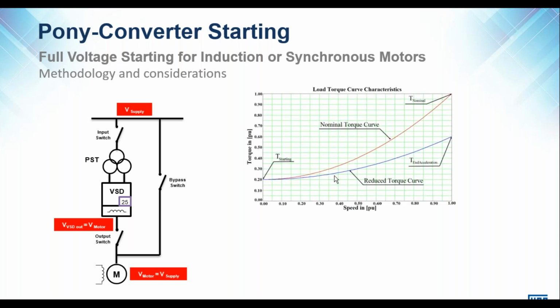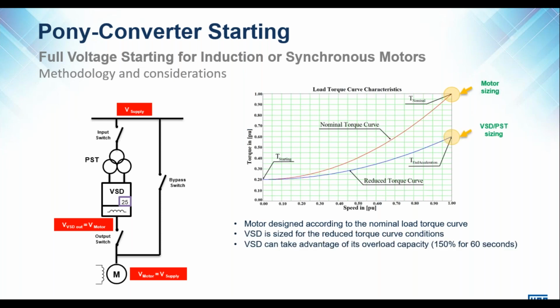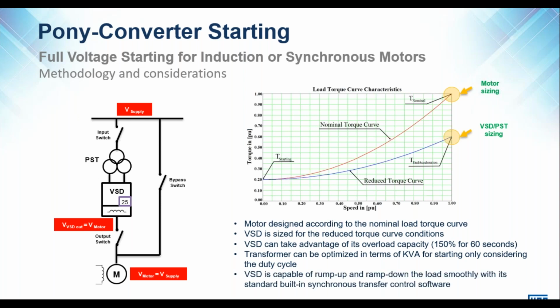This curve you recognize from earlier. We have the blue curve, which is a load that accelerates up to the end of acceleration, but the full load is not necessarily yet applied. In this case, the motor would need to be designed for the full load condition. However, it is theoretically, or rather practically, possible to design the VSD, if it is only used for starting, at a reduced rating. So from a CapEx point of view, this can dramatically reduce the outlay or the cost involved.